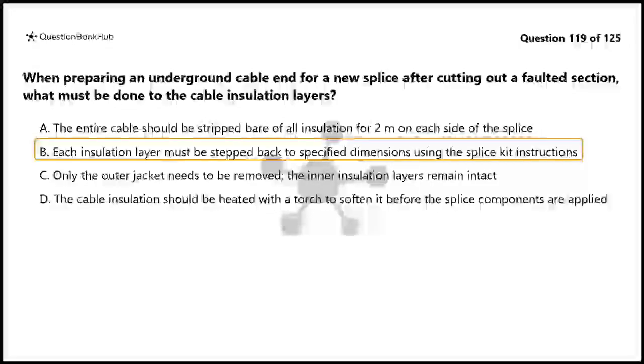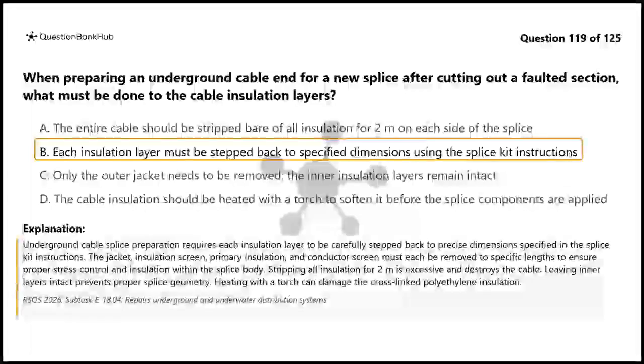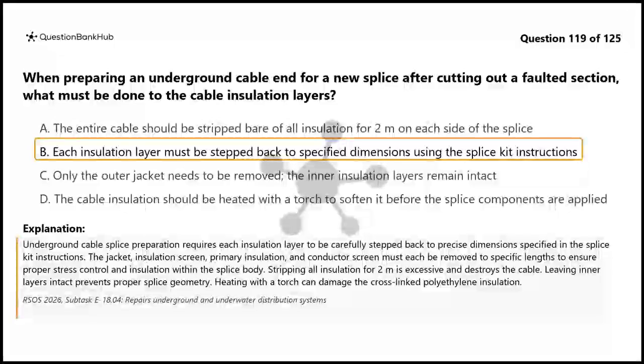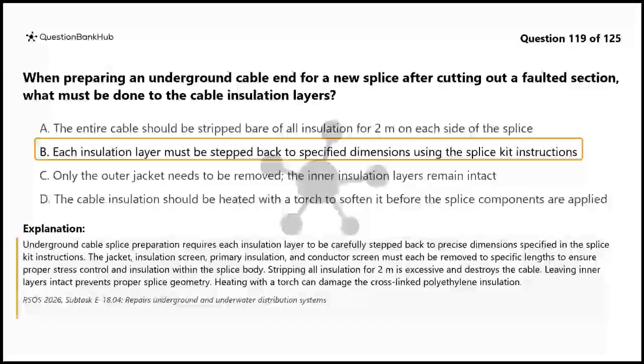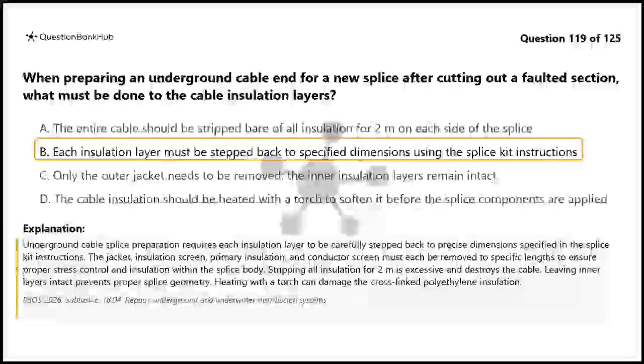The correct answer is B. Underground cable splice preparation requires each insulation layer to be carefully stepped back to precise dimensions specified in the splice kit instructions. The jacket, insulation screen, primary insulation, and conductor screen must each be removed to specific lengths to ensure proper stress control and insulation within the splice body. Stripping all insulation for 2 meters is excessive and destroys the cable. Leaving inner layers intact prevents proper splice geometry. Heating with a torch can damage the cross-linked polyethylene insulation.